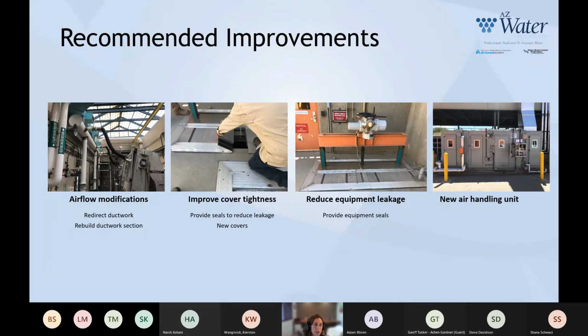So our recommended improvements included changes to the airflow. We redirected some ductwork. We rebuilt a ductwork section. We also recommended improving cover tightness. I mentioned that analogy of sucking through a straw. If you increase that tightness, then when you suck, there's something there to fight against it and allow it to draw. And then we also recommended a new supply air handling unit to supply air to the west end of the fine screen room, which is where I mentioned the fine screen hopper and the grit washing station are located.